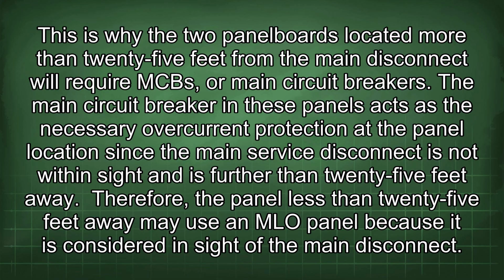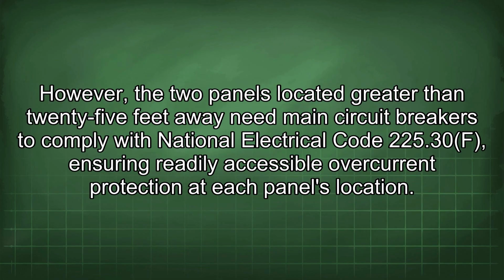Therefore, the panel less than 25 feet away may use an MLO panel because it is considered in sight of the main disconnect. However, the 2 panels located greater than 25 feet away need main circuit breakers to comply with National Electrical Code 225.30f, ensuring readily accessible overcurrent protection at each panel's location.